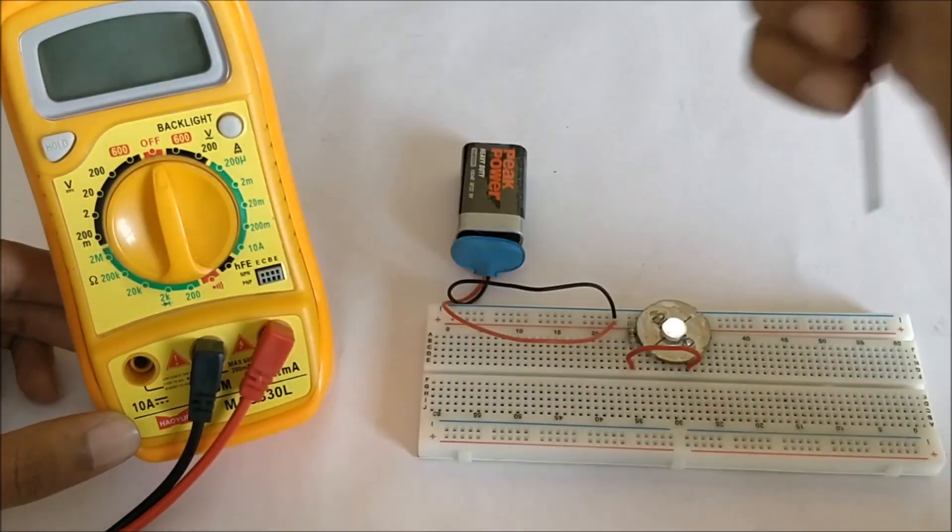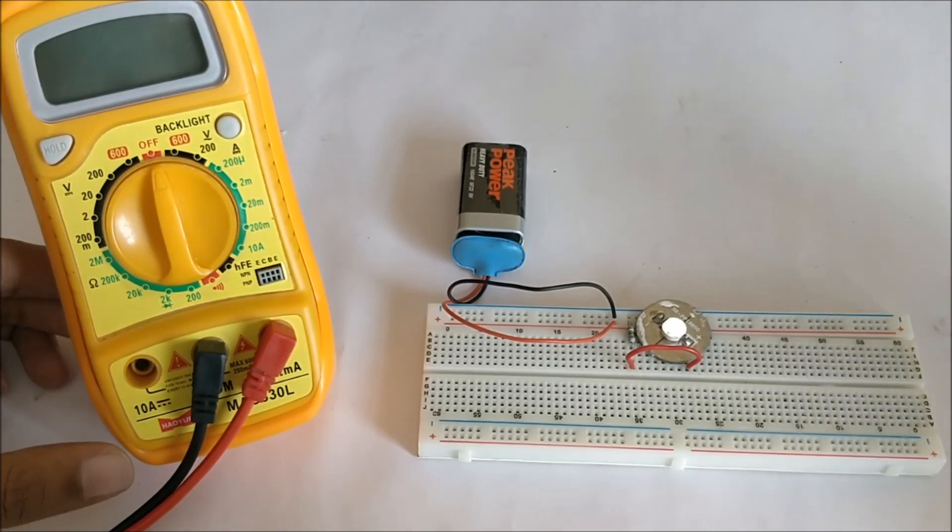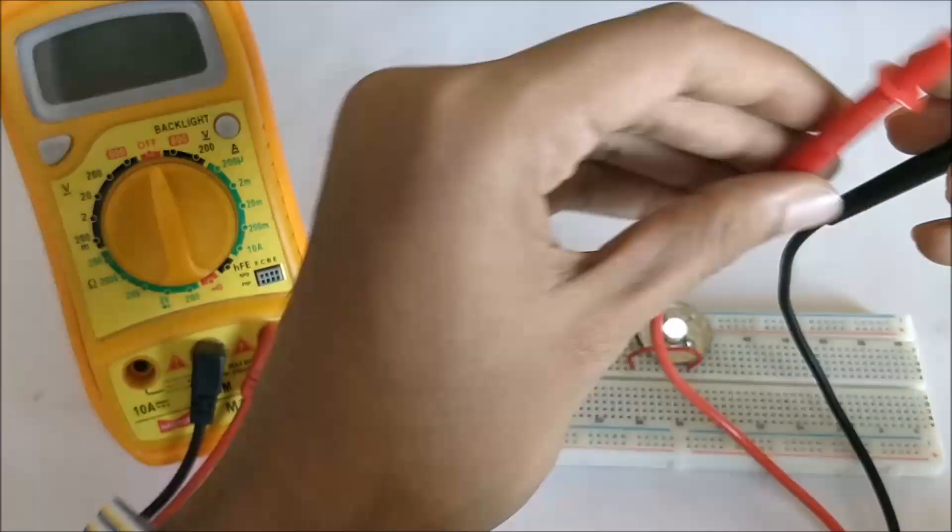Since the current here that we are measuring is very small, we are using the slot that is to our right side. But do note, when you are measuring a higher current device, you have to use the slot that is to your left side. Otherwise it would cause a fuse failure in your multimeter.